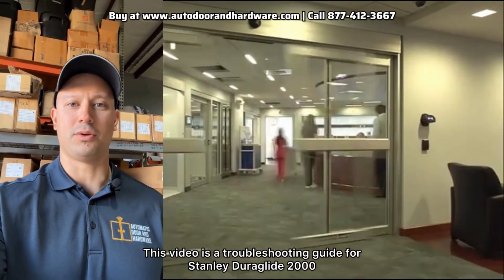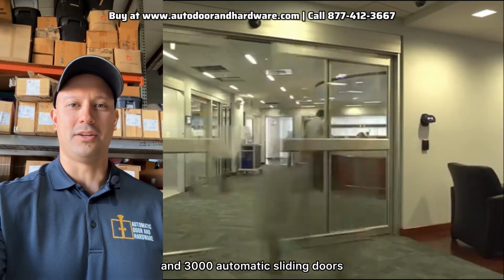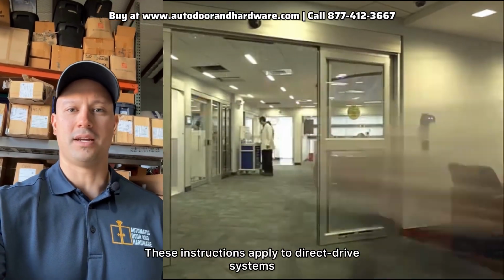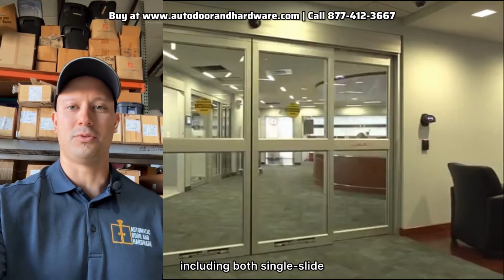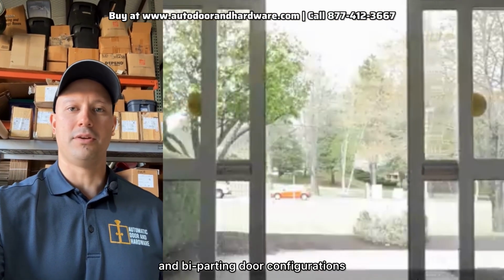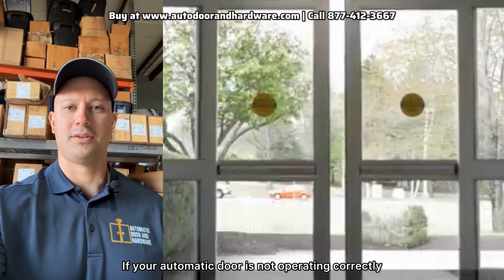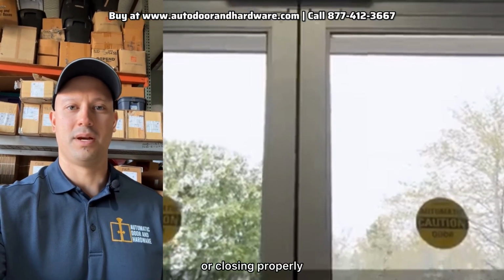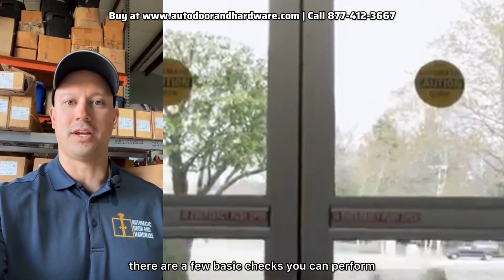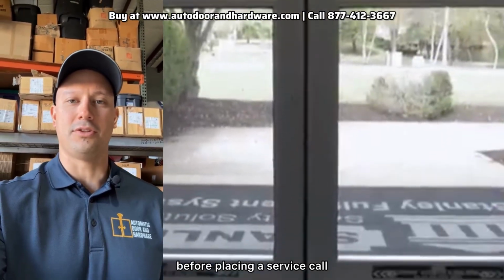This video is a troubleshooting guide for Stanley DuraGlide 2000 and 3000 automatic sliding doors. These instructions apply to direct drive systems, including both single slide and biparting door configurations. If your automatic door is not operating correctly, meaning it is not opening or closing properly, there are a few basic checks you can perform before placing a service call.